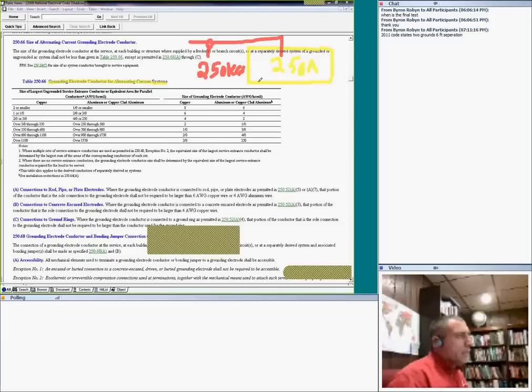And then I need to go size my equipment on the conductor. Here's my ground, here's my neutral. I need to go from the ground all the way to Mother Earth, so I tie to my ground right here. How do you size the grounding electrode conductor? The question that comes to mind is how am I going to size this conductor. Let's look at 250: it goes between over 3/0 and under 350. If they don't tell you otherwise, you're using copper. Cross-referencing with copper, that conductor will be number 2.